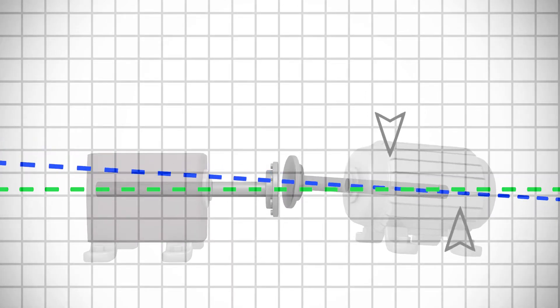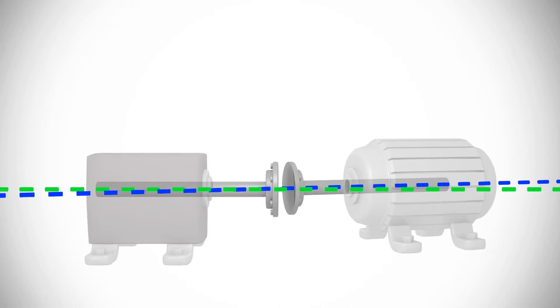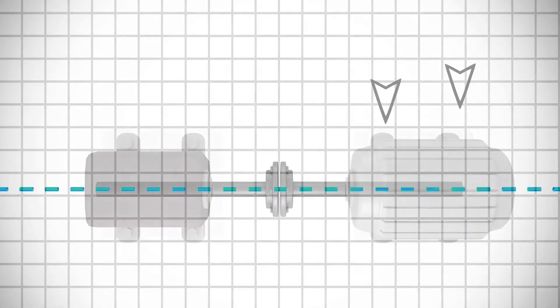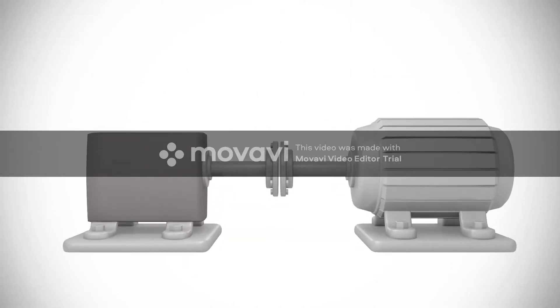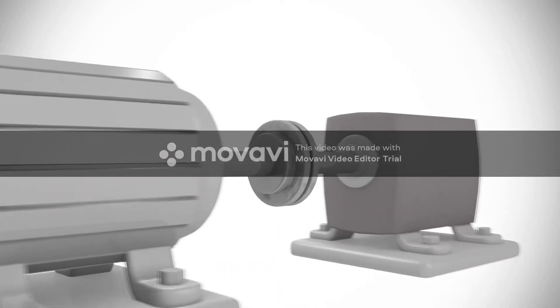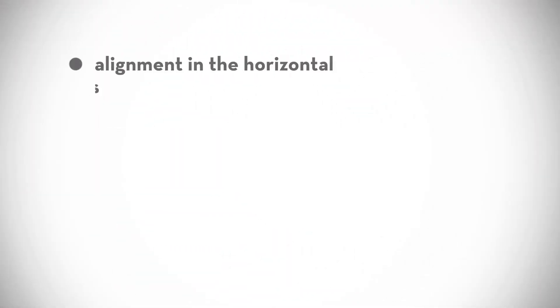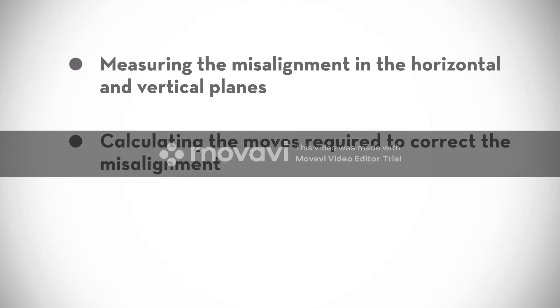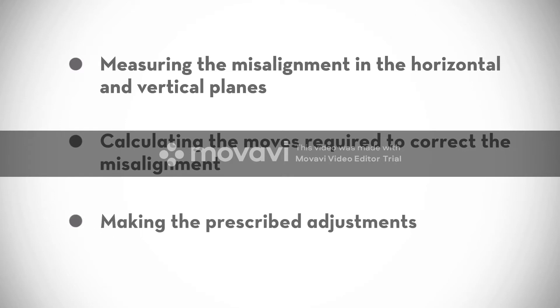We can raise and lower the moveable machine in the vertical plane, and we can move it side to side in the horizontal plane. If we get the shafts aligned in these two dimensions or planes, they will then be in tolerance and close to collinear. The challenge of precision alignment can therefore be defined as: first, measuring the misalignment in the horizontal and vertical planes; second, calculating the moves required to correct the misalignment; and finally, making the prescribed adjustments.